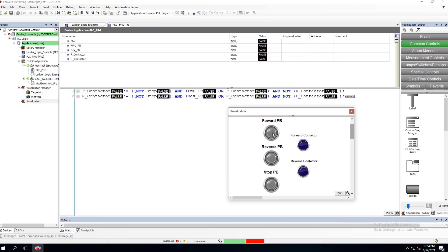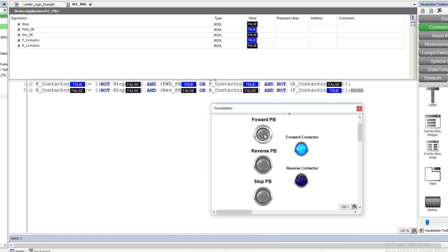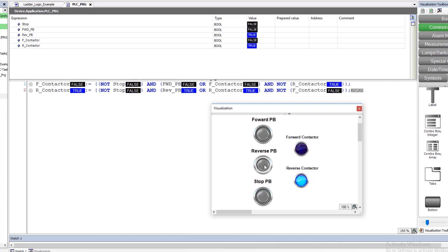Let's do some testing. Forward turns the forward on, let's turn the reverse — make sure it works exactly like our ladder logic version. We cannot turn our reverse on while forward is running. Turn the stop, then turn on the reverse so the reversing contactor comes on. Let's try to turn our forward button on — that doesn't work, just like it should. If the reversing starter is on, the forward shouldn't come on, and vice versa.